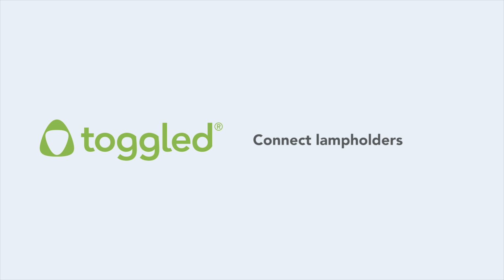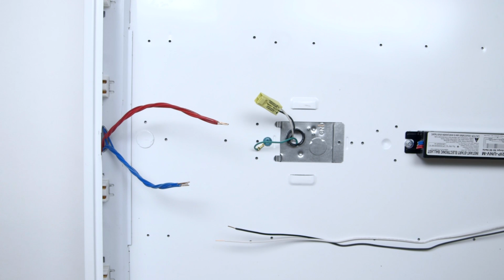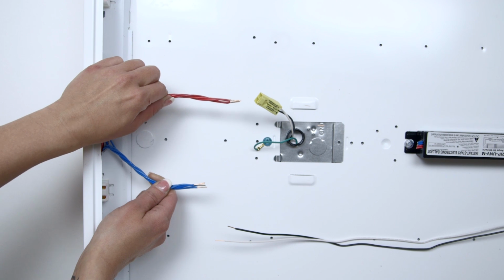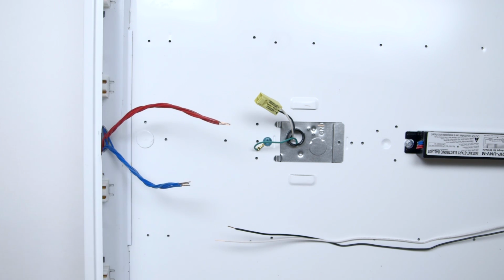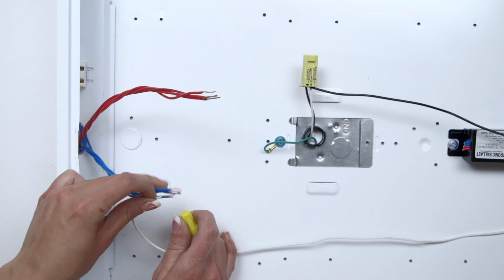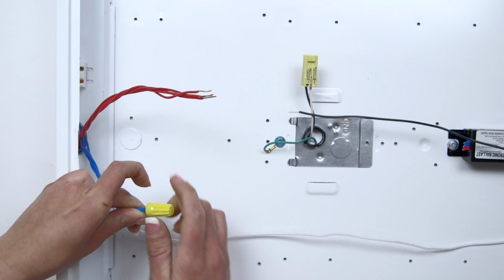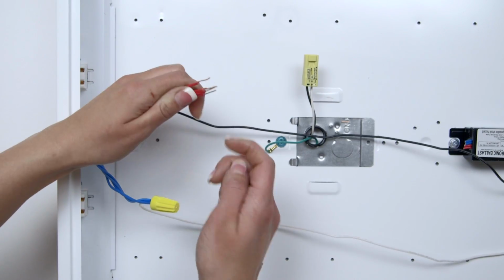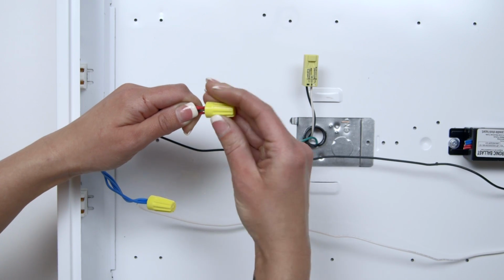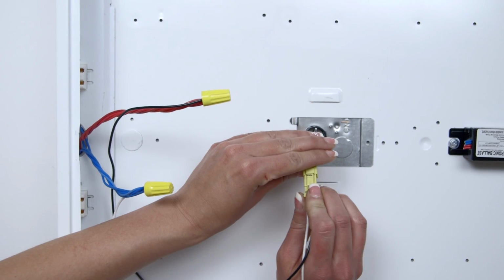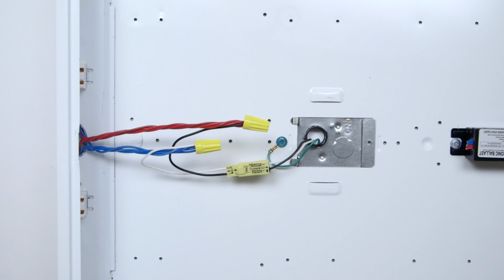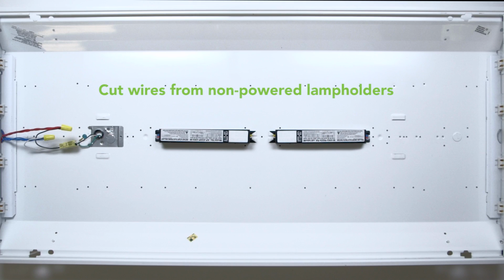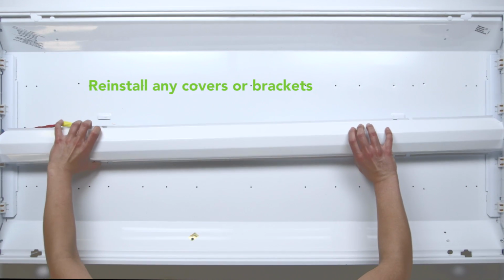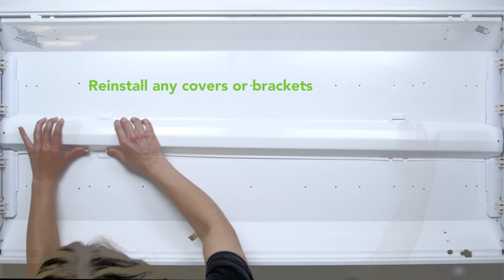You will now connect one wire from each lamp holder to line and one wire to neutral. It can be helpful to gather wires from the lamp holders into two groups, one from one side of the lamp holders and one from the other side. These two groups are then separately connected to line and neutral using the provided wire nuts. Ensure the fixture remains grounded. At the non-powered end, cut all wires from the lamp holders. Reinstall the ballast cover and any other covers or brackets which hold the lamp holders in place.